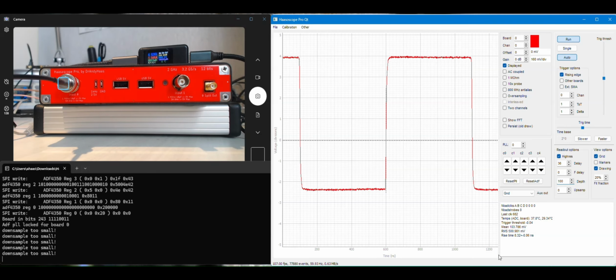The downside is you can't record the data as quickly, so right now, even while we're recording it, we're getting about 60 hertz drawn to the screen, which is about 0.6 megabytes per second taken out of the scope.